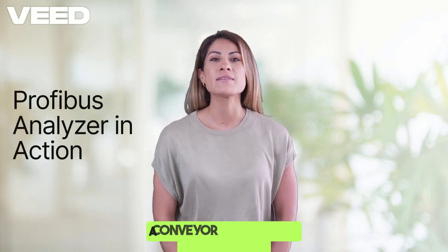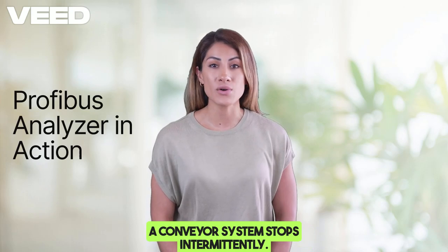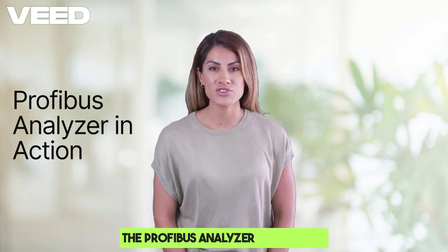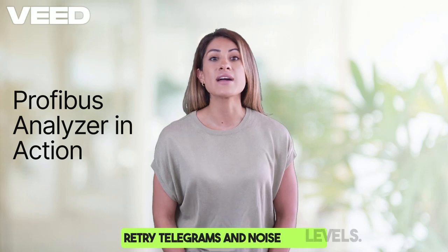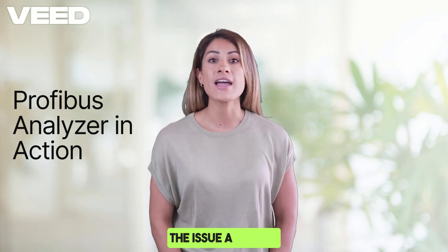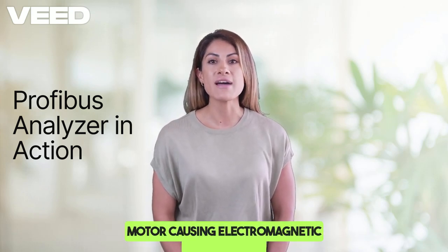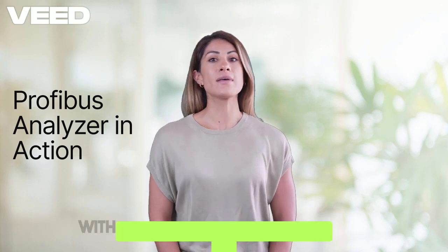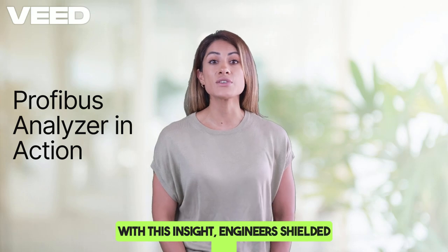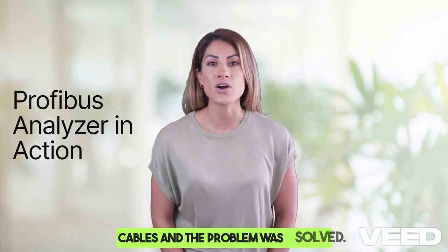Real example. Imagine a factory where a conveyor system stops intermittently. The Profibus Analyzer shows high retry telegrams and noise levels. The issue? A nearby motor causing electromagnetic interference. With this insight, engineers shielded the cables, and the problem was solved.